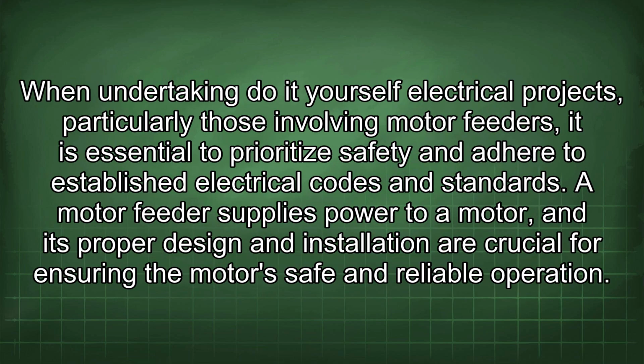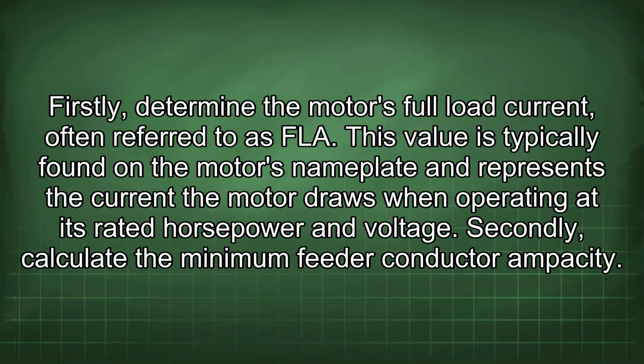When undertaking do-it-yourself electrical projects, particularly those involving motor feeders, it is essential to prioritize safety and adhere to established electrical codes and standards. A motor feeder supplies power to a motor, and its proper design and installation are crucial for ensuring the motor's safe and reliable operation. Firstly, determine the motor's full load current, often referred to as FLA. This value is typically found on the motor's nameplate and represents the current the motor draws when operating at its rated horsepower and voltage. Secondly, calculate the minimum feeder conductor ampacity.